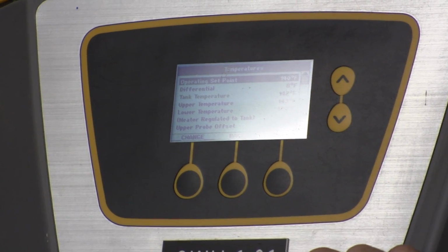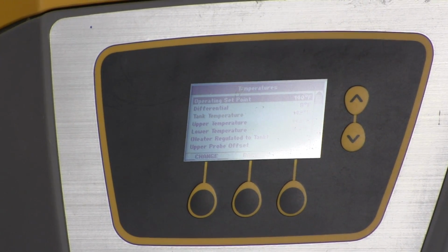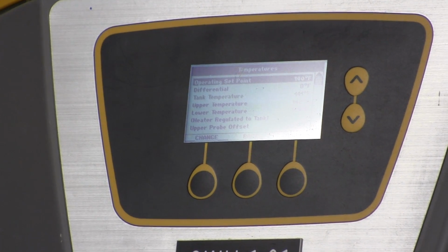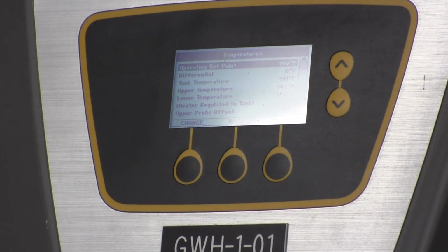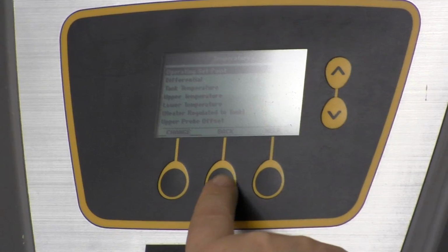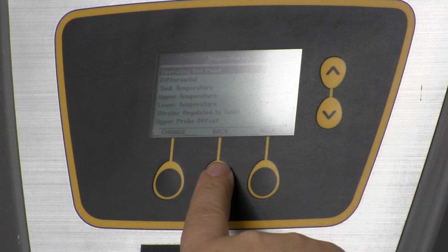Can I ask you a question about temperature? Yes. Is it set at 140 because of code? Because it's connected to the kitchen. Well, the way it's designed, the kitchen loop needs 140. It needs 140 for your dishwasher and for sanitizing. So you could put this down to 120. Yeah, but your mixing valve's doing that for you. Yeah, the point is energy saving.